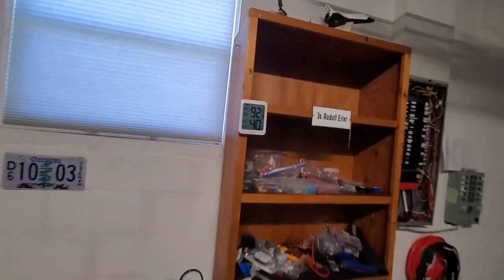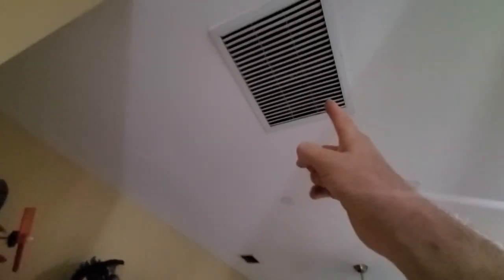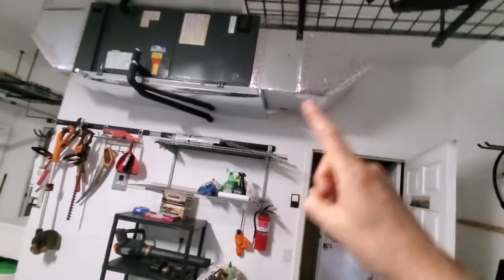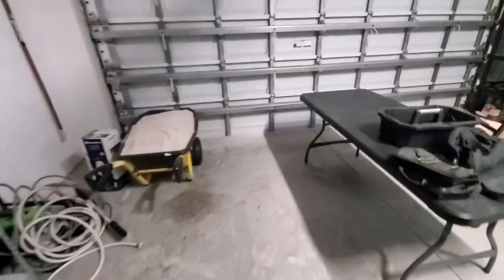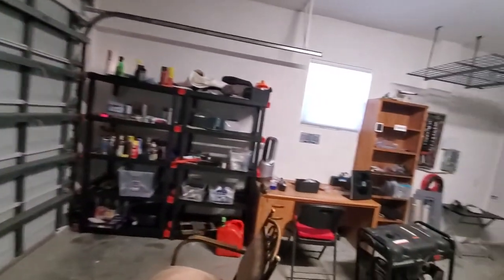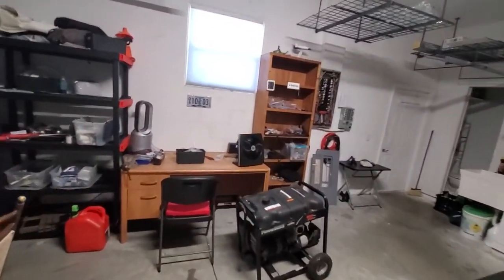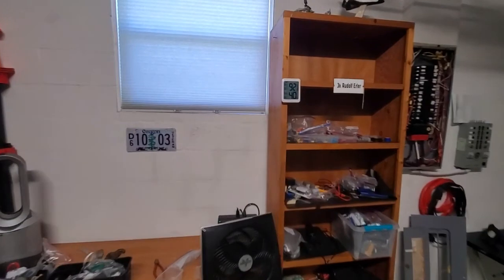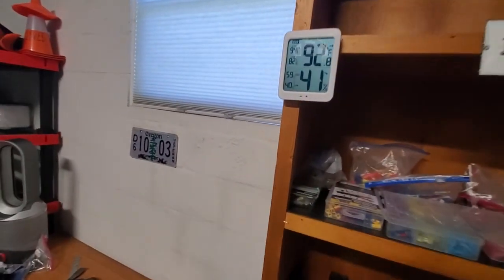A couple minutes later, 40%. So what's happening is hot air is coming into the house and going up through that return, back through the attic and into here, just looping right there. That's a bit inefficient for the air conditioning since the distance is so short. It's about 93 degrees outside and inside, but it's feeling better in here because although the temperature only dropped 1 degree, the humidity's gone down 10%, which makes a huge difference in comfort.